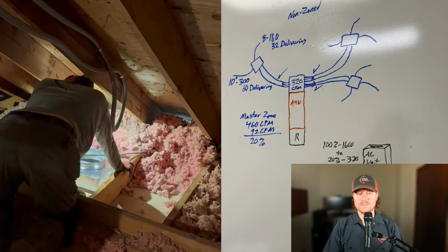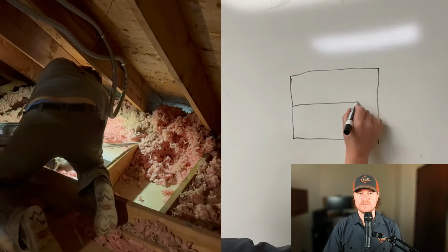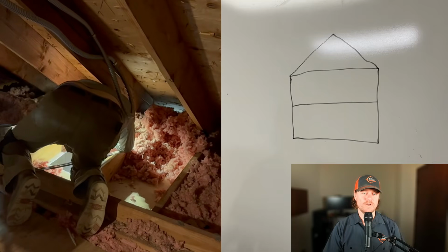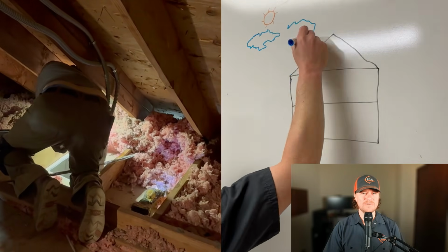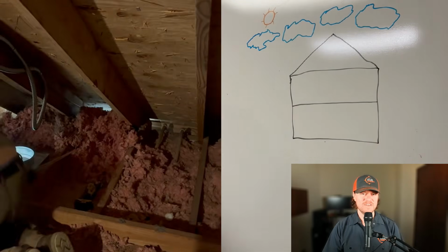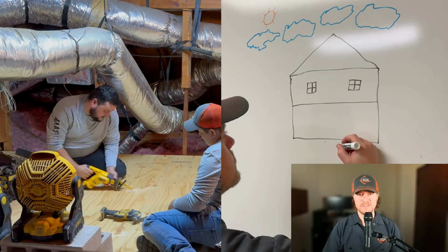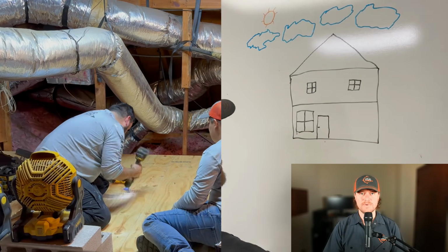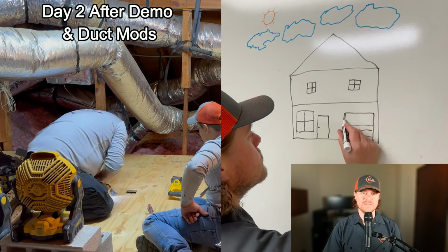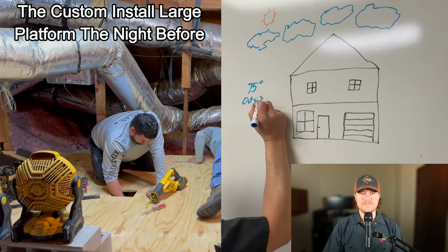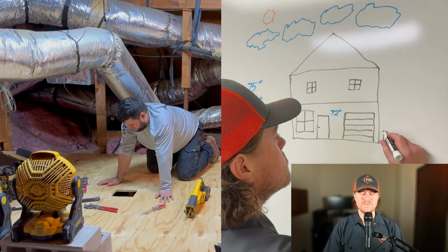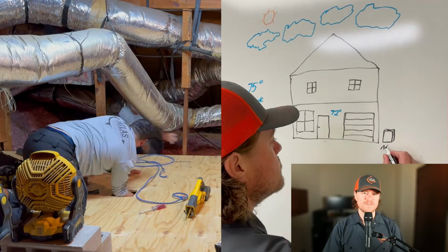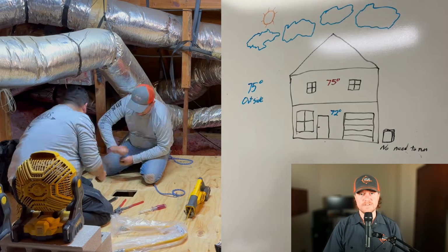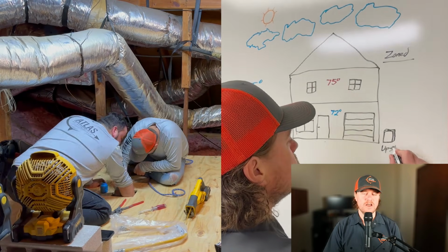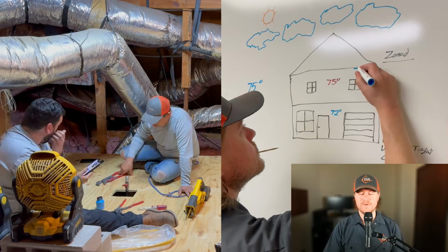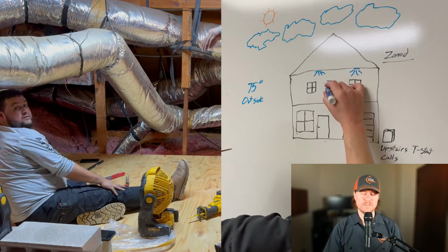The first one, which is the one that I like the most, is how it handles the shoulder season. This is the time frame when it's really nice outside and your AC or heater really doesn't run very much. And it ends up making my house feel stagnant or dingy. And when I'm running the system when it's non-zoned, the thermostat is downstairs with the smallest heat load, so it ends up not running very often. And the upstairs will get a bit warmer or colder, ending up being a delta there. When I have the system zoned, the upstairs ends up running more often, which eliminates a lot of this problem, helping to keep it from feeling stale. Because of this, you also end up with better filtration throughout the entire year.